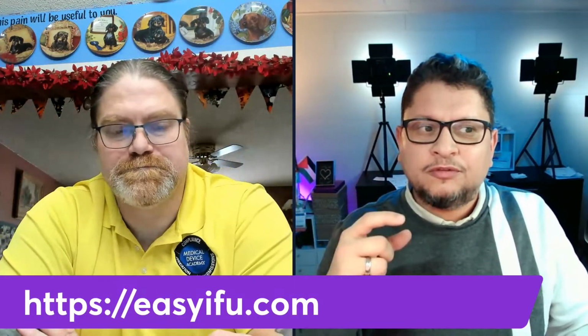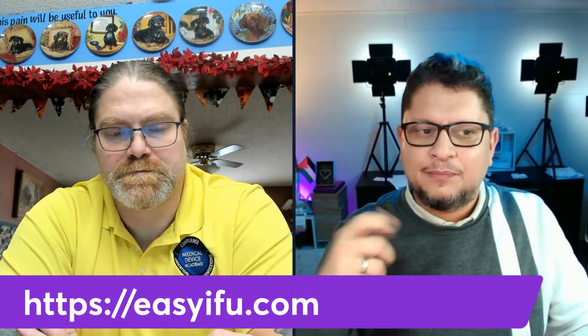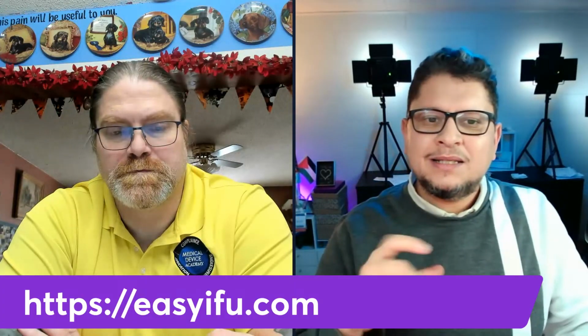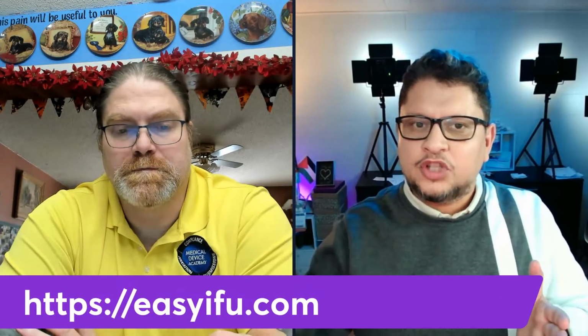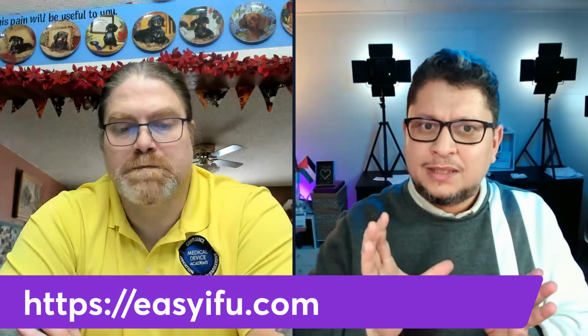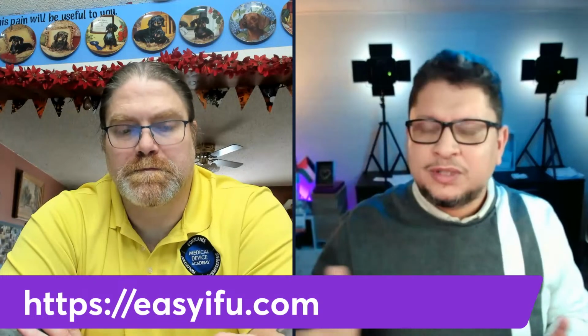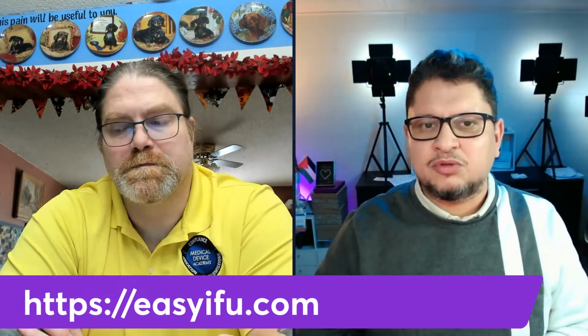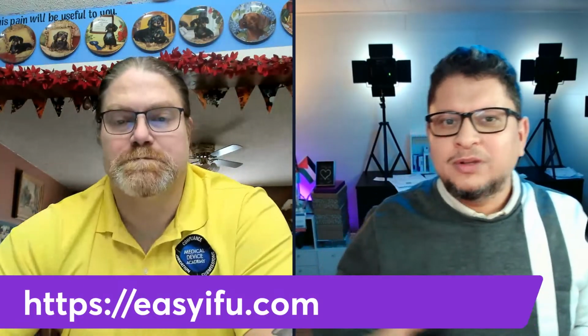So a lot of countries are now moving to the eIFU system, or willing to accept eIFU. So our idea is that instead of you creating 10 eIFUs differently, one for Japan, one for that, let's find the requirements of all those countries and ask you to fulfill all those requirements, and then you are safe for all the countries. So no need to create one specific for each country. You can still do it. It's just an extra thing to avoid all this logistic.